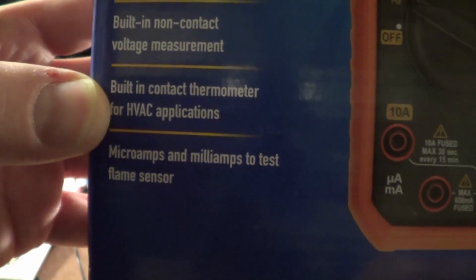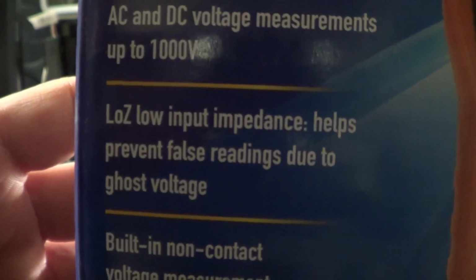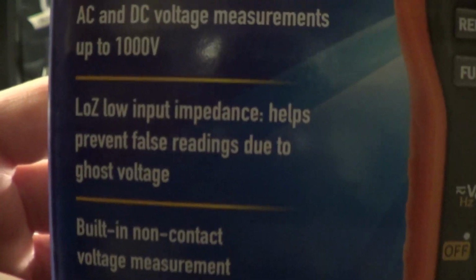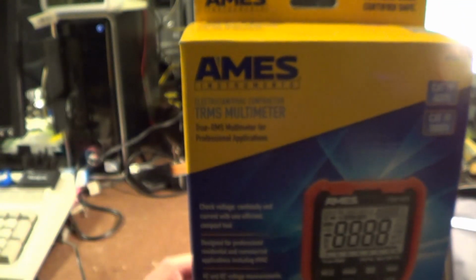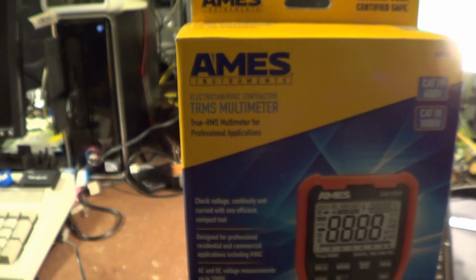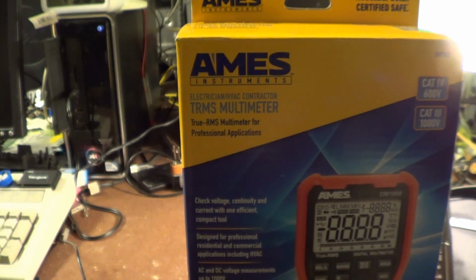One of the most interesting features in this block of descriptive text is the low Z, low input impedance setting. Some multimeters have this, most of them do not. Basically, a good example of its use would be to imagine that you have several wires run through a conduit of some kind, and let's say that 3 of the 4 are actually carrying electrical power. What can sometimes happen is that a phantom voltage can be induced on any idle wires inside the conduit. So if you take a multimeter, which is normally a high impedance or high resistance instrument when it's measuring voltage, you can be led to believe that there's a significant voltage there when in reality it's nothing. If you loaded it down to any significant degree, it would disappear or even be greatly attenuated.